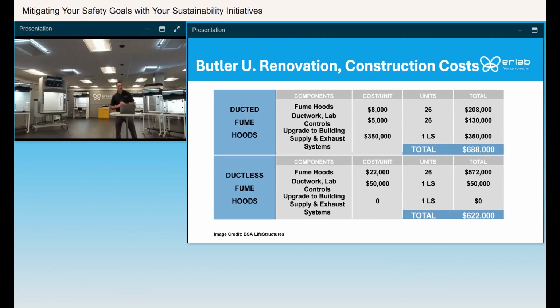This was one of our first large projects with our green fume hood back in 2011. They had 2 5-hood chemistry teaching labs, which did not have enough hoods for all their students. They had HVAC capacity problems, so they had poor indoor air quality within the space. So they're hoping to get up to 26 total fume hoods from the 10 they had, so 5 in each lab. So they looked at going ducted. And if they were to go with 26 ducted fume hoods, they were going to have to upgrade their entire HVAC system for a lump sum of about $350,000. So they looked, how could they do that for less money?